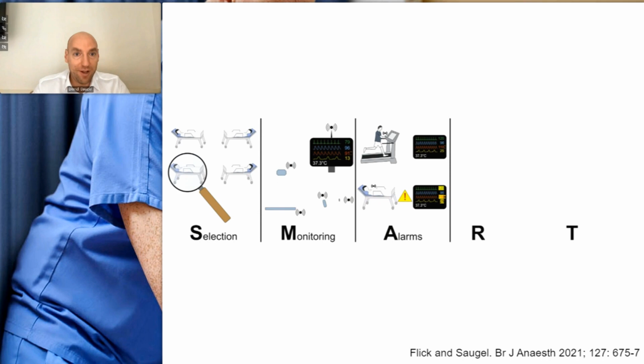It's a difference whether a patient is lying in bed or is having physical therapy. And for example, for patients with chronic respiratory lung disease, a saturation of 92 may be perfectly fine, versus a saturation of 92 may be a bad sign for a young and healthy patient. This is what I mean when I say that alarms need to be contextualized and individualized for each individual patient.